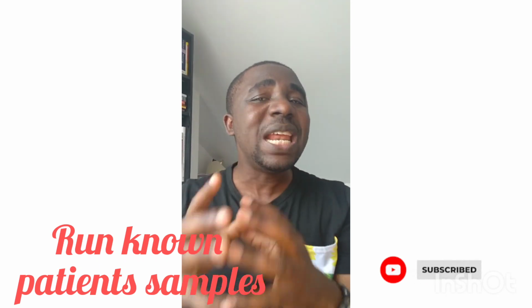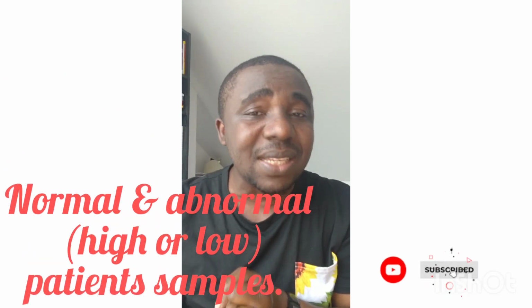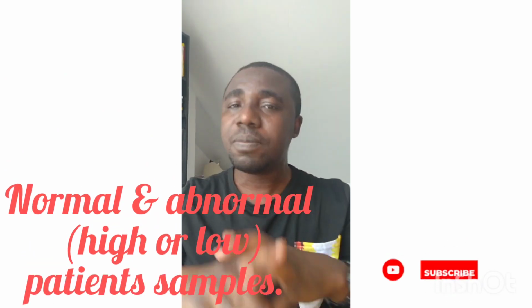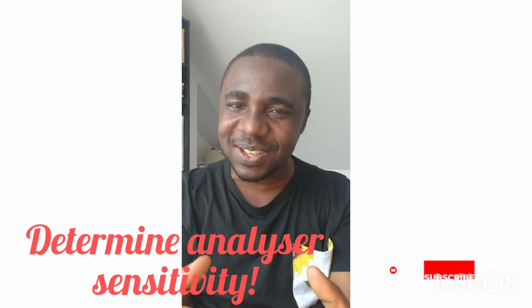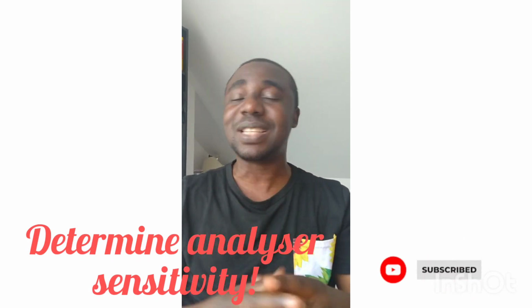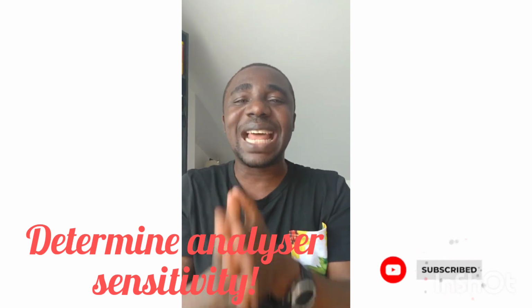Following the control passing, you can then run the patient sample. You're going to run both normal patient sample and abnormal patient sample, abnormal high or low. Why do you run both normal and abnormal, low or high? Because you want to see how sensitive the analyzer is when a result is abnormal. You want to know the analyzer is able to give a reliable result whether it's normal, low, or high. That's why you run the patient sample as normal, abnormal high, and abnormal low.